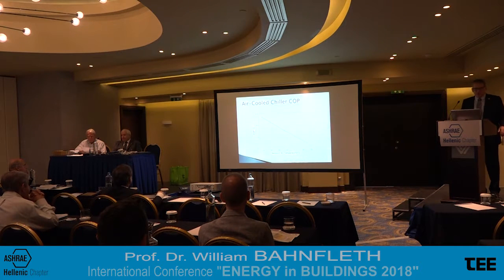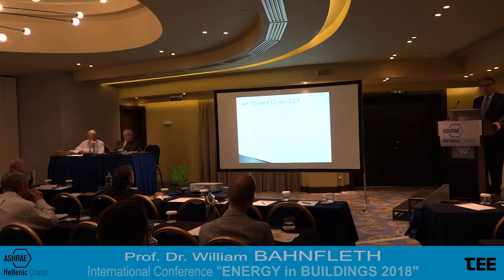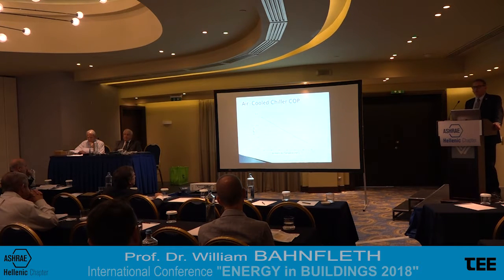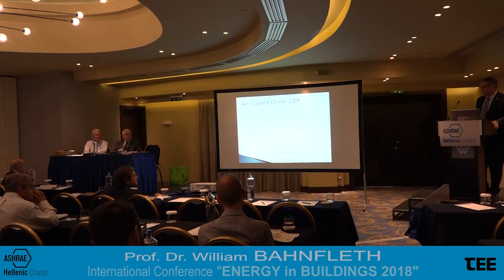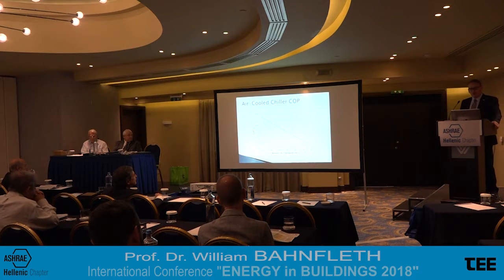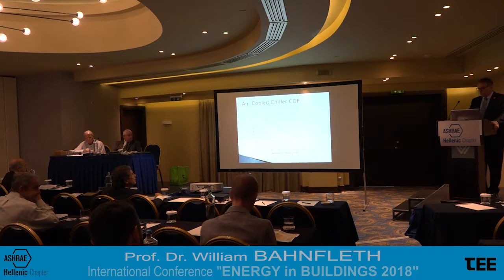So here are the chiller characteristics that I used for this example. It's less efficient than something you get today because this is a few years old, but the thing to point out here is how much the COP increases as the ambient air temperature decreases, and that's what we're going to take advantage of here in this example. So essentially what we did is run that cooling load profile through this chiller model using the temperature profile that was shown, and did that both with and without storage.